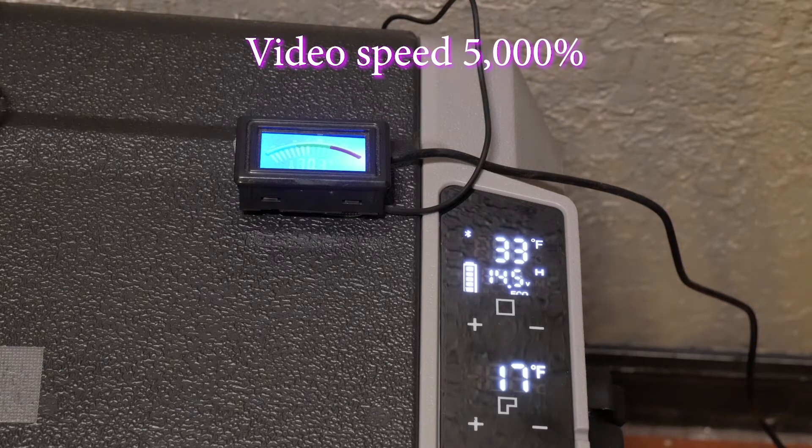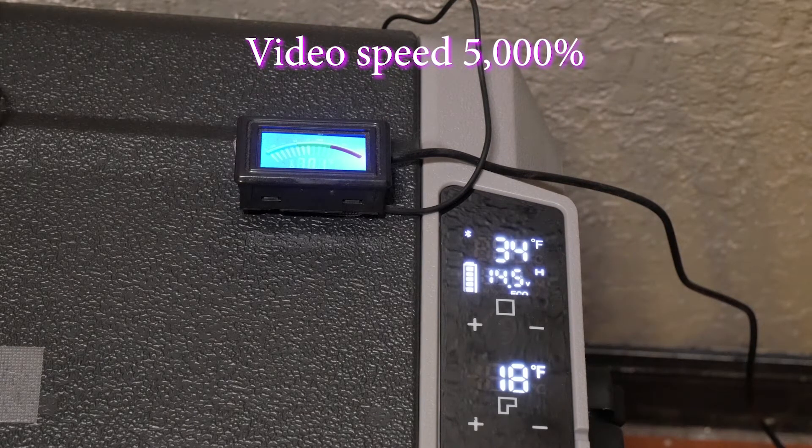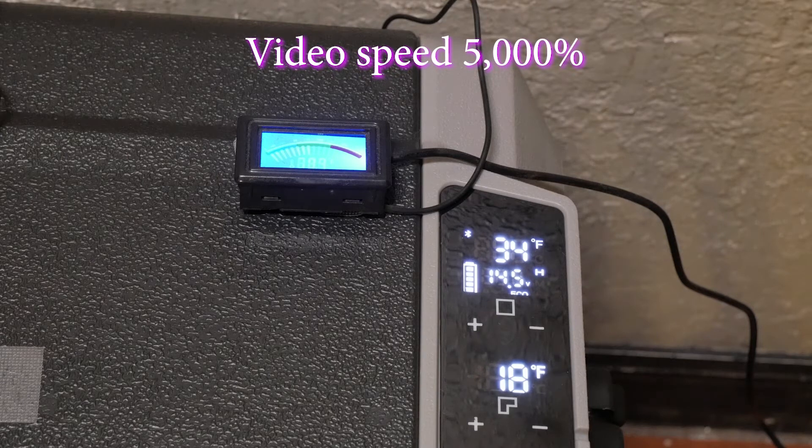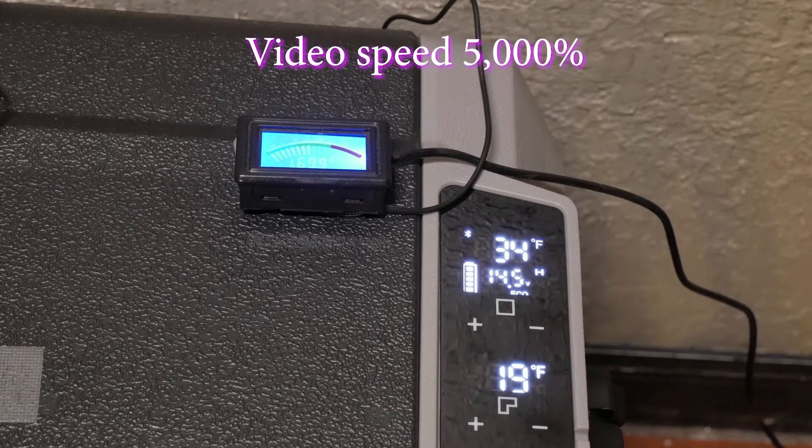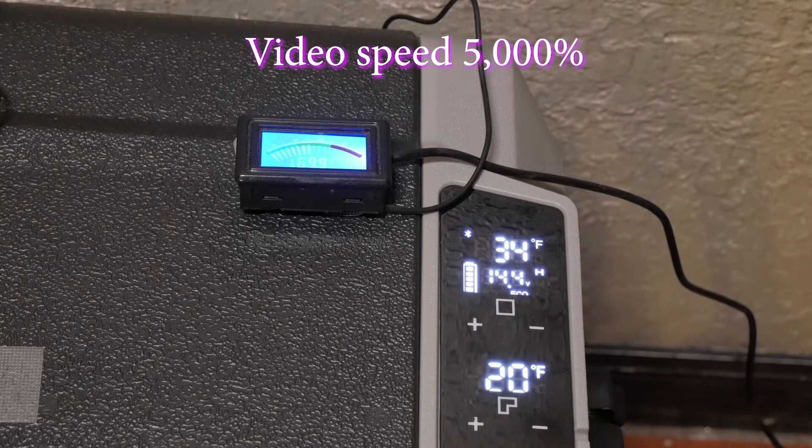In 7 tests with the unit turned off, it took on average 1.5 hours for the internal temps to reach above 40 degrees, the freezer side seeing an average increase of 34 degrees within 2 hours.